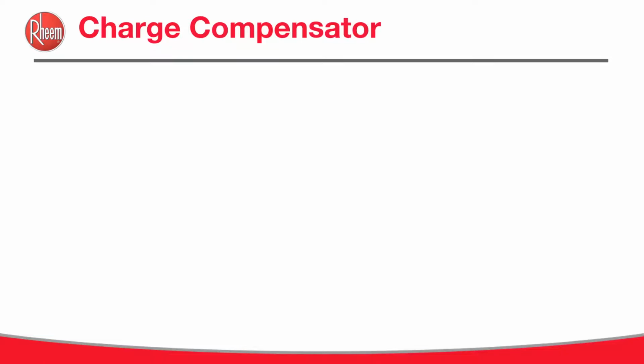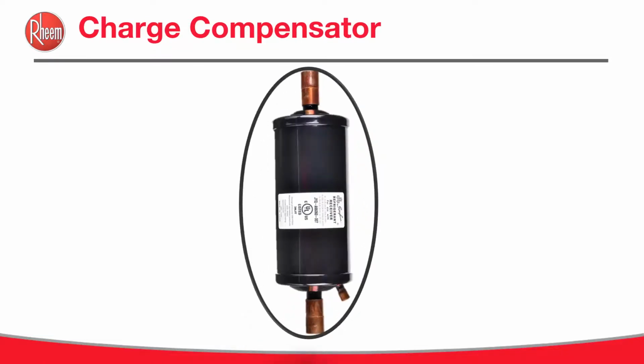Charge compensator. So charge compensator you may or may not have seen. This is basically a storage tank used for charge and balance between heating and cooling modes. So yes, you guessed it. It is not used in an air conditioner. It is only used in heat pumps, and certain models may require it. So what does this mean? The indoor coil and outdoor coil may not be the same size, right? So sometimes you may not have the same size coil indoors and outdoors. So in some instances, you may have extra refrigerant, which is not required in the system, and it is stored in the charge compensator. So let's look at different locations for the installation of the charge compensator.